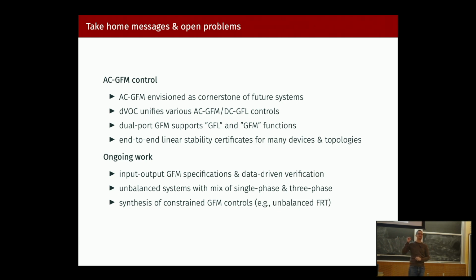So now, what happens with this paradigm if you say, let me not even have wind, because that gives significant inertia using this control. Let's just say we're only using PV, distribution connected. All of these inverters have like 5 to 10 milliseconds worth of rated power stored internally, so that's not a lot. So your frequency starts fluctuating a lot faster, but your prime mover is also many orders of magnitude faster. Where the time constant of a synchronous machine turbine is anywhere between 4 and 12 seconds, the time constant of a PV module behind these things is 1 or 2 milliseconds.